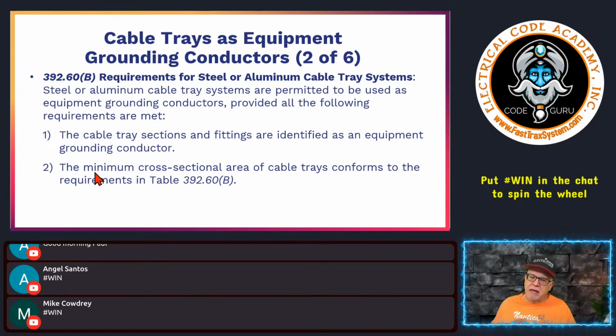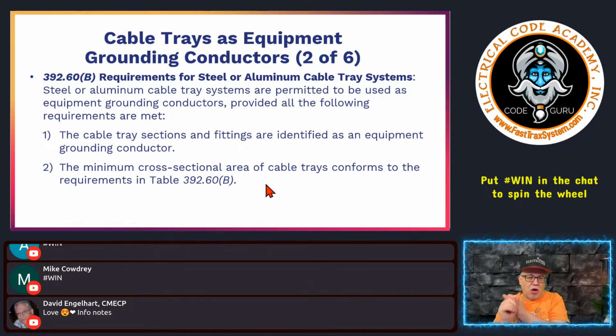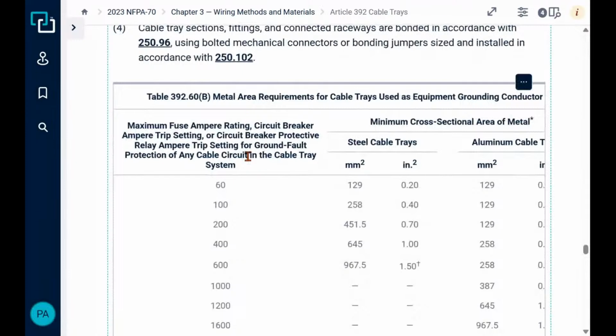Secondly, for those identified for use as an equipment ground, the minimum cross-sectional area of a cable tray conforms to the requirements of 392.60(B). So it has to meet all those requirements in 392.60(B). And I will show you that really quickly, what it means by that. And here you see B right here. So see this table?